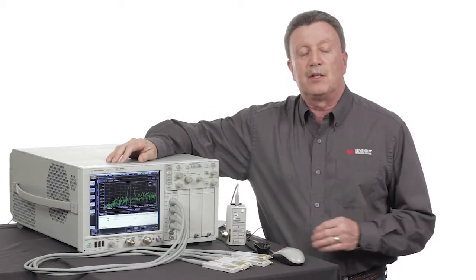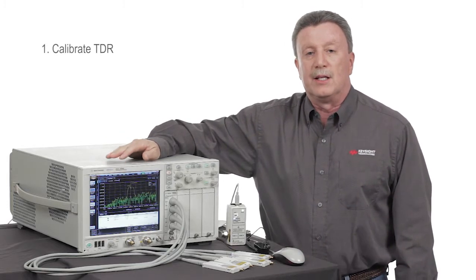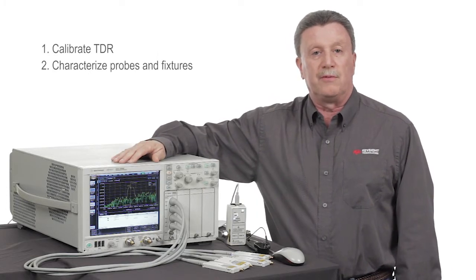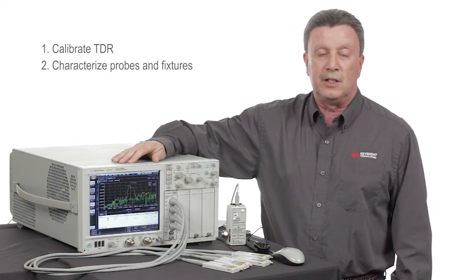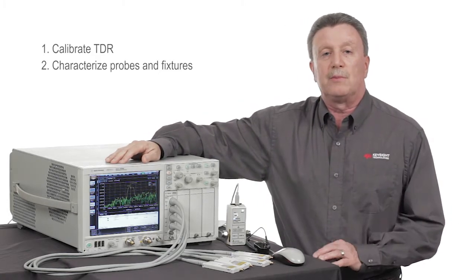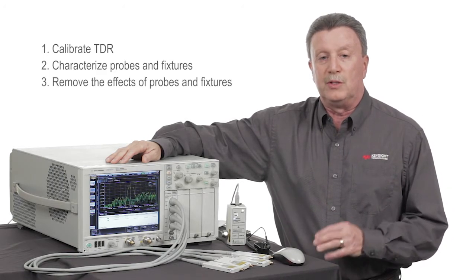And there's three steps to the process. The first step is to calibrate the TDR. The second step is to use the calibrated TDR to characterize the probes and fixtures that you need to use to connect to your DUT. And the last step is to measure the DUT plus the probes and fixtures and then remove the effects of those probes and fixtures through de-embedding.